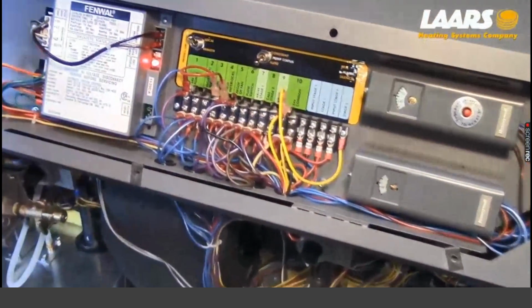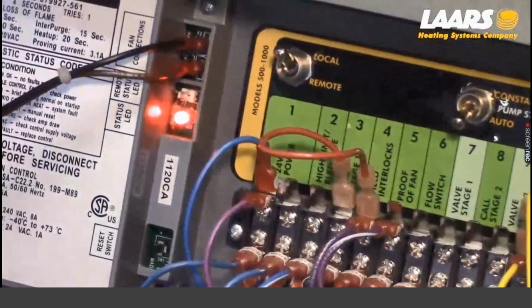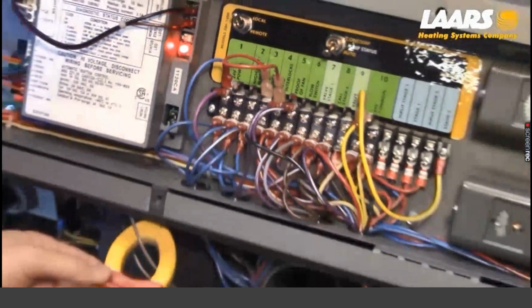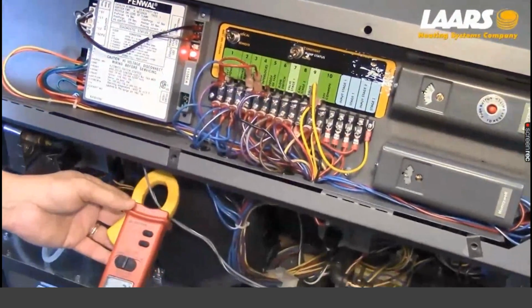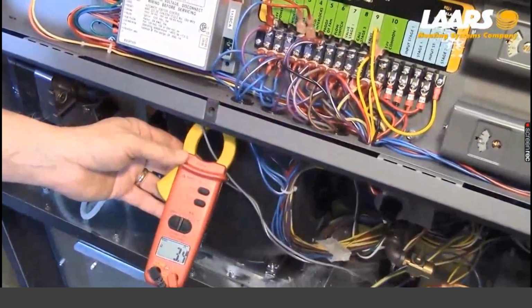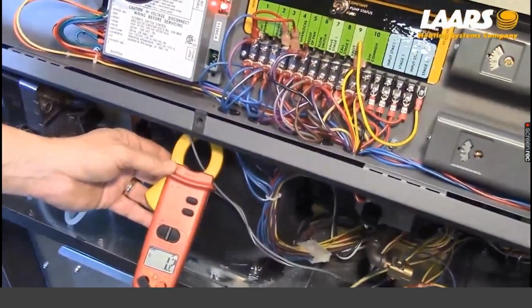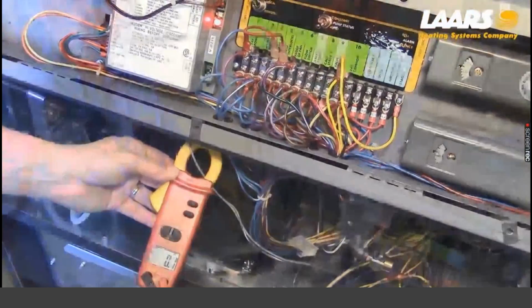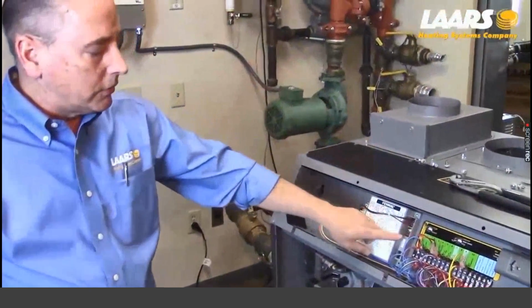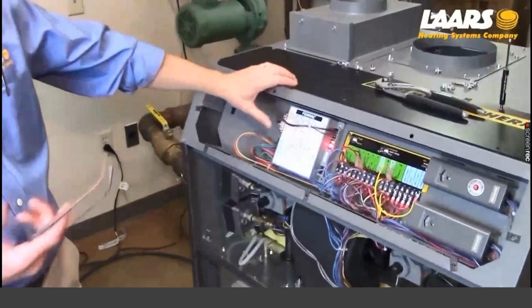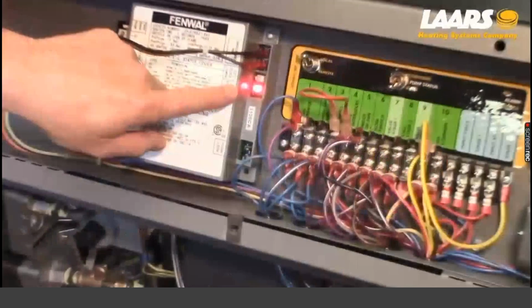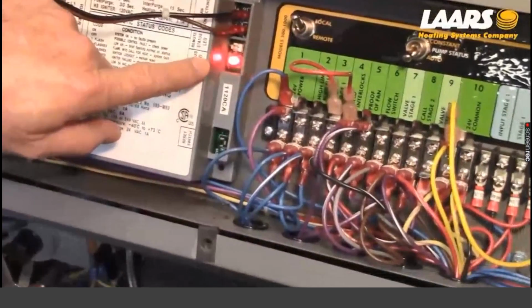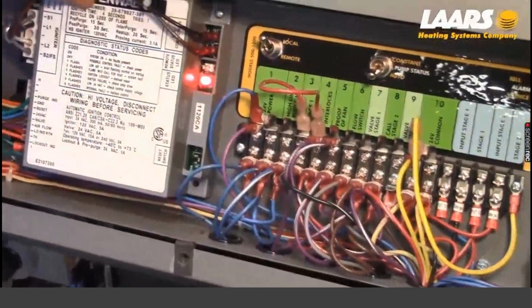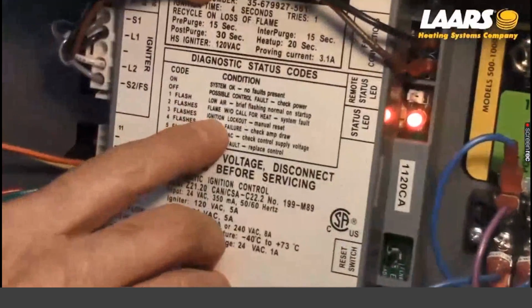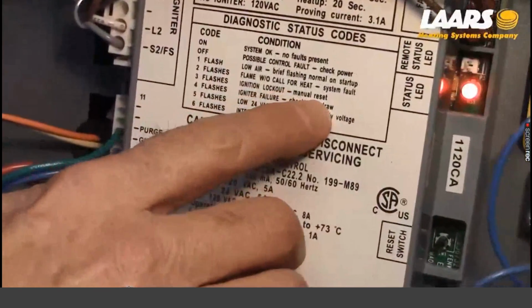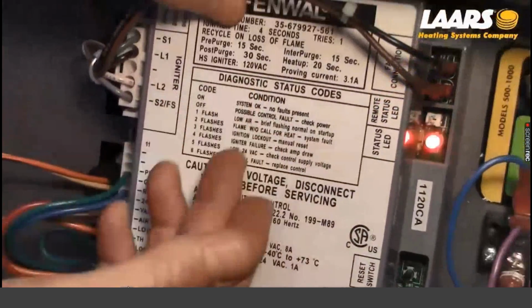you'll see that single flash. That's telling me my igniter is now being energized. I'm going to put an amp probe on there, and we're looking for 3.4 amps or greater. And now we just lit off. Okay, lastly, I just want to talk about the ignition control and the fault codes. So, as we can see right here, we're flashing 3 flashes. And when you look on the codes here, 3 flashes will show you ignition lockout. It's a manual reset. So here are our codes.